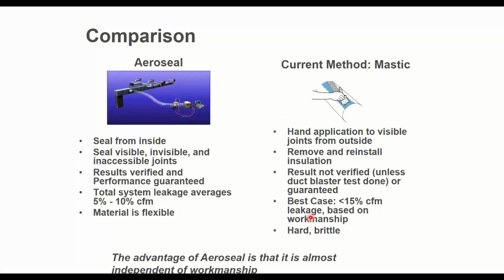So, advantages of this technology over doing it by hand, such as mastic. Mainly I'm comparing it to mastic because in the case of welding and stuff like that, you're in a whole different category of building, and a specific, you know, specialty project. But mastic would be the common method for commercial buildings and even residential. So the advantage of the Aeroseal really is that you're sealing it from the inside out, which means you don't have to physically get to the ductwork. It can be behind drywall and paneling and shafts and ceiling and all that stuff. You don't have to get there. You just have to get somewhere where you can make one injection point on the duct. And after that, you can do it all from the inside out. That's the real advantage of it.